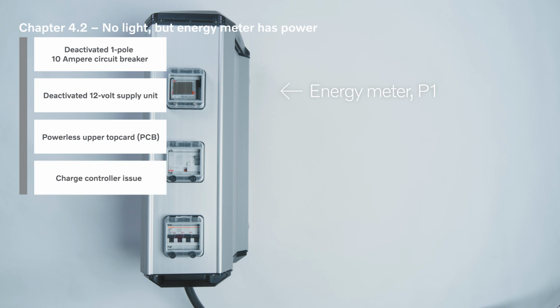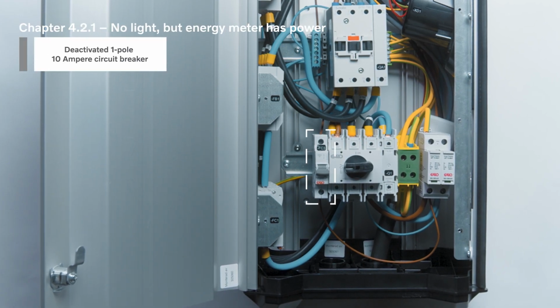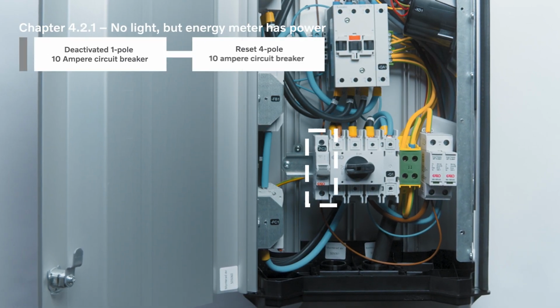When operating the charger, the charge controller should always blink green. If the 12-volt power supply unit has power, but the charging controller still doesn't indicate green, this can be caused by a bad connection between the DC terminal and the upper top card, or that the charge controller doesn't receive power or is malfunctioning. If the issue is caused by the 1-pole 10 ampere circuit breaker, you should reset it.